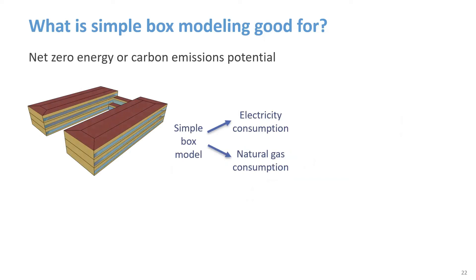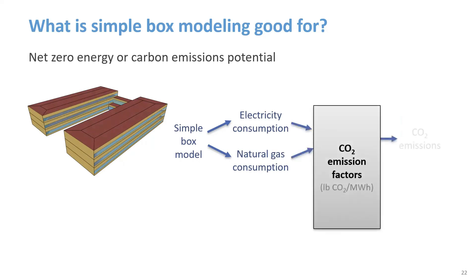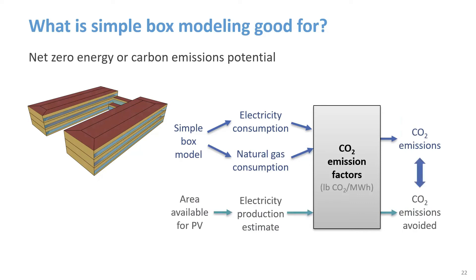A simple box model can also be used to check if a concept design is on track for net zero energy or net zero carbon emissions. The model provides an estimate of electricity and gas consumption, and CO2 emission factors can translate that into CO2 emissions. A separate calculation can estimate energy production from on-site photovoltaics and the corresponding emissions avoided, showing whether you're on track or need to reduce energy consumption or increase the area available for a PV system.